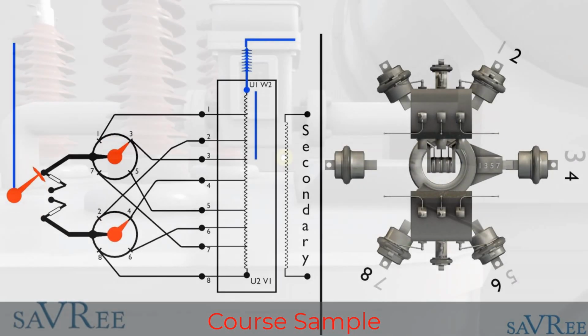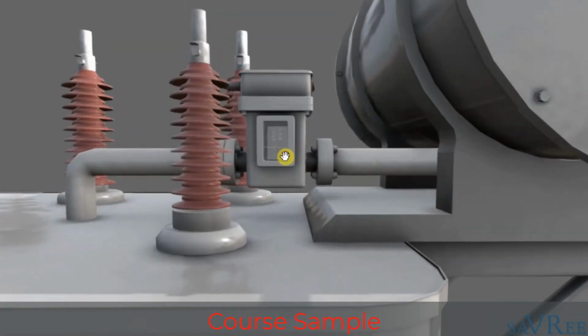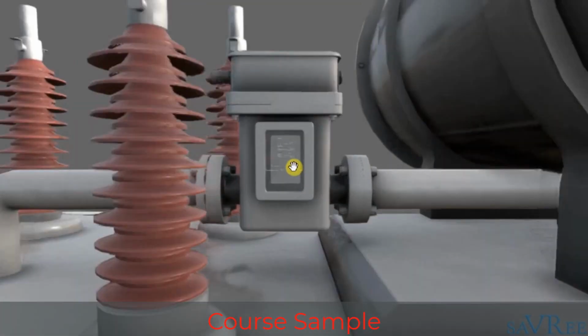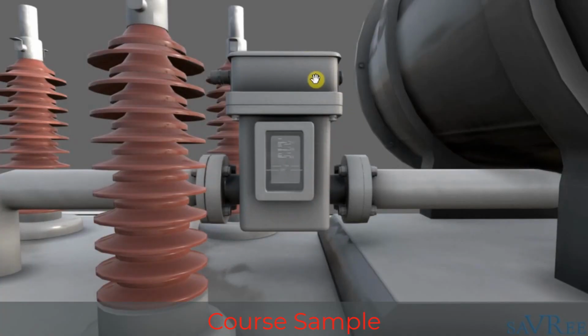This is the gas actuated relay, contained within this square box. You may also have heard the term Buchholz relay, although the Buchholz relay and the gas actuated relay are slightly different. A gas actuated relay protects against small electrical faults within the transformer and large electrical faults within the transformer.